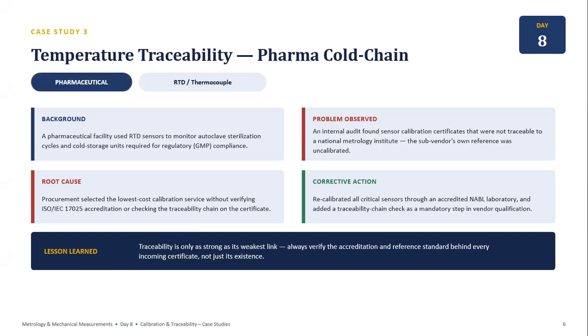The third case study focuses on RTD sensors used in pharmaceutical applications, including sterilization processes and cold storage facilities. An internal audit revealed that some calibration certificates were not traceable to a national metrology institute. The reference used by the sub-vendor itself was not adequately calibrated. The root cause was the selection of a low-cost calibration service without verifying the ISO accreditation and without checking the traceability chain behind the certificate.